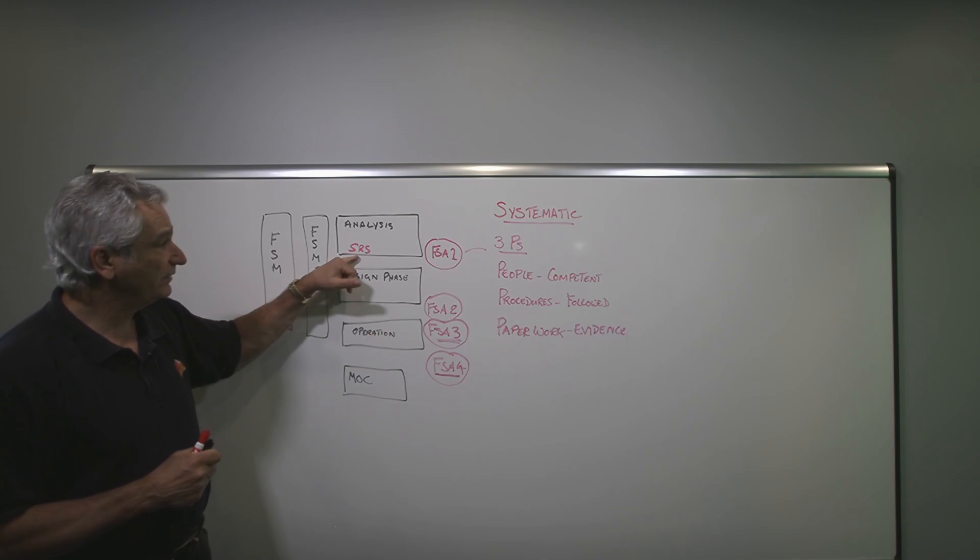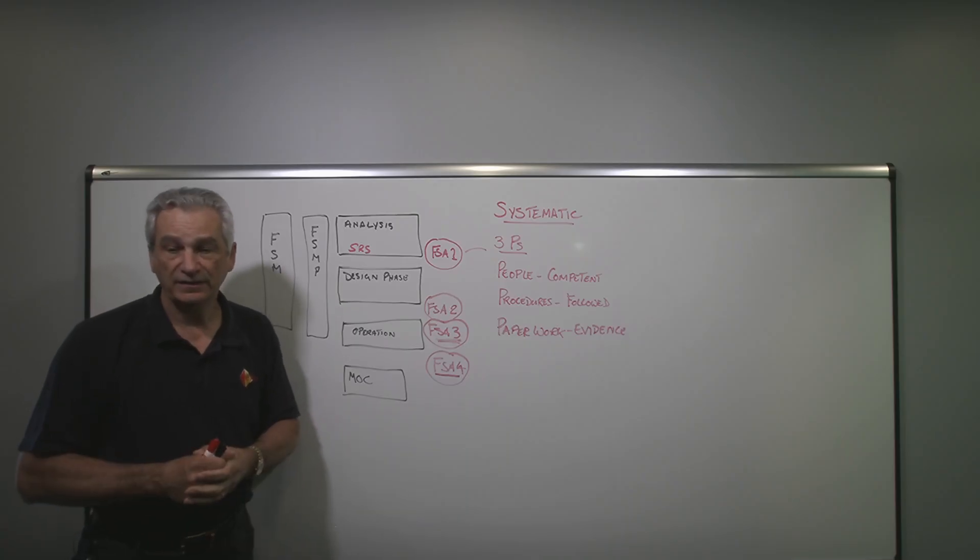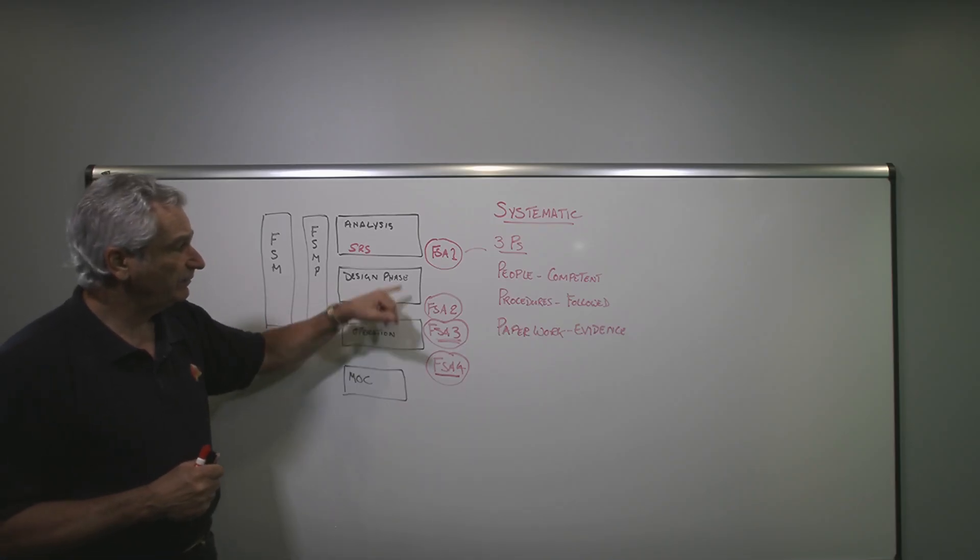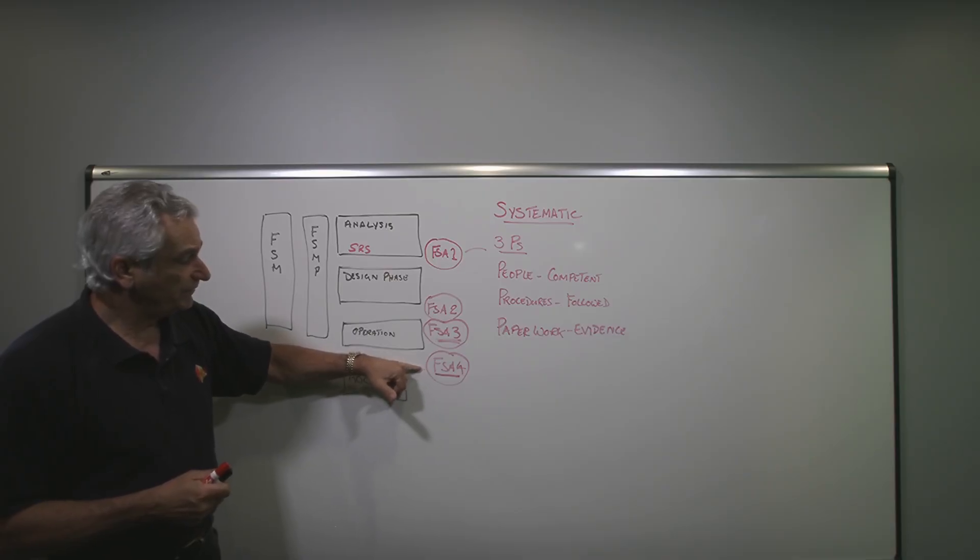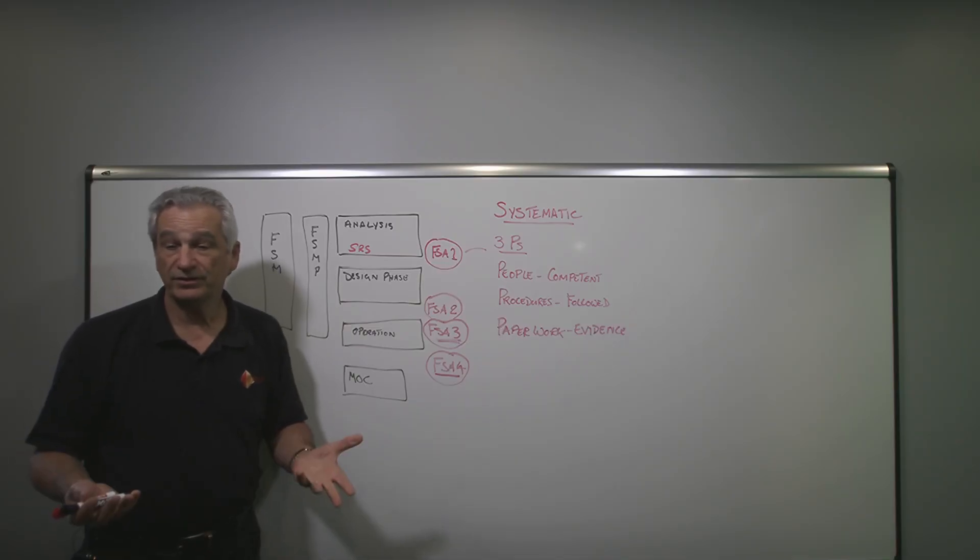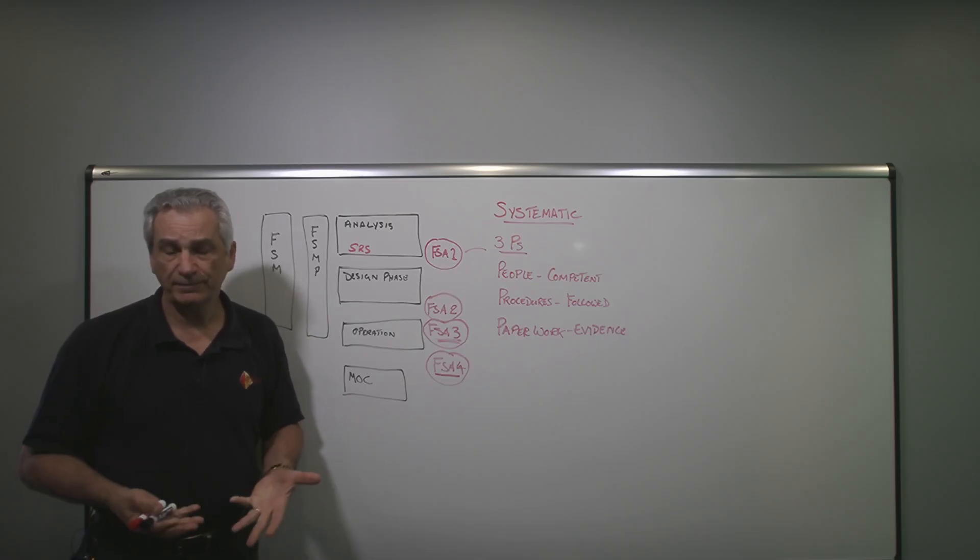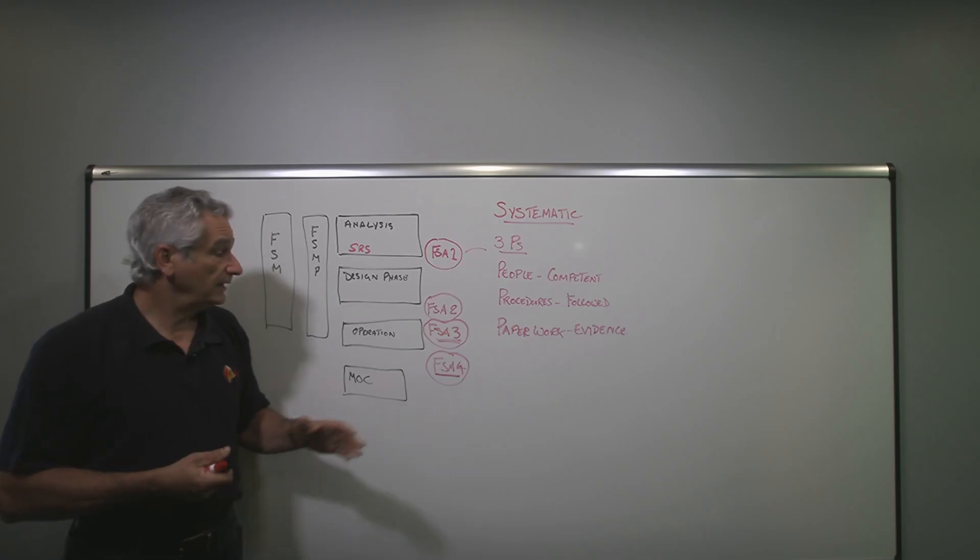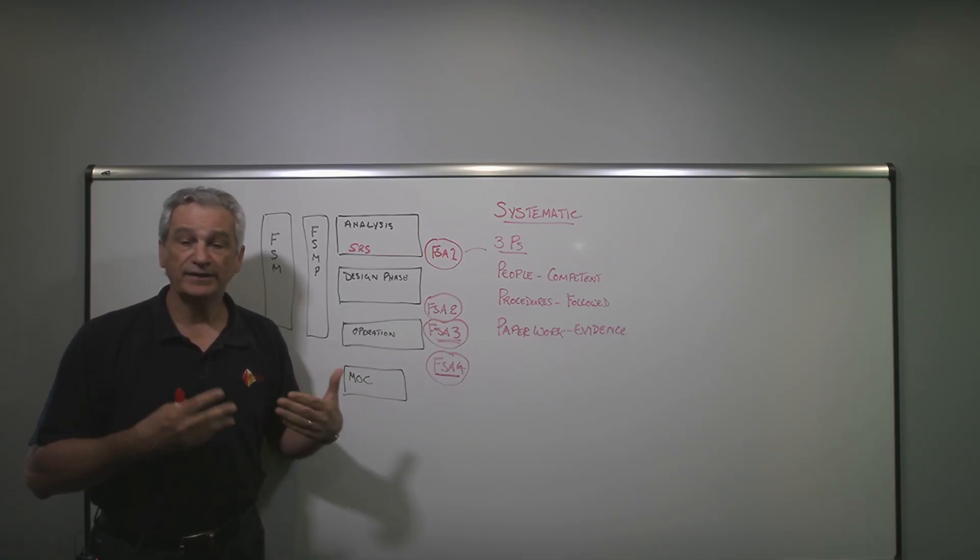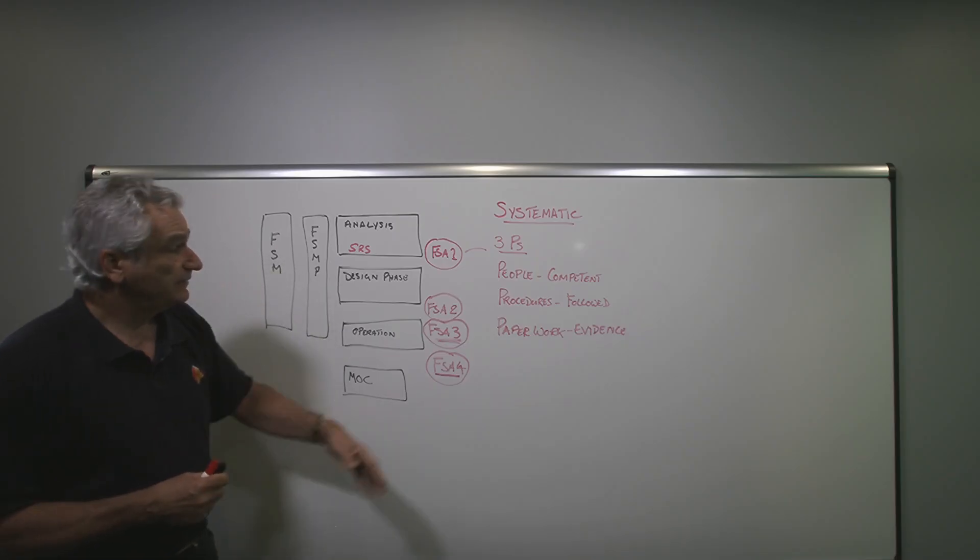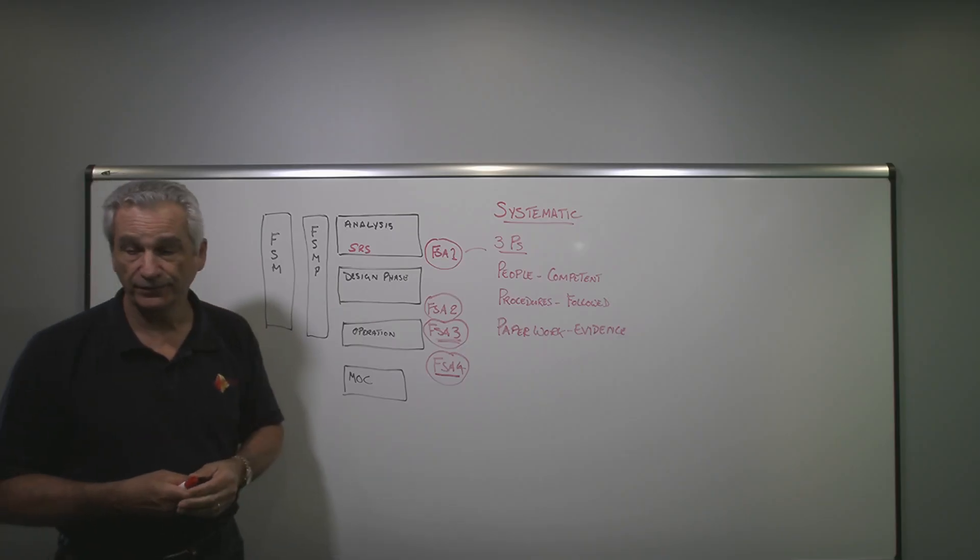We need to be able to look at our performance metrics. We can get a lot of the performance metrics from the SRS, such as the proof test interval, the mean time to restore, the mean time to fail safe, the spurious trips, the demand rates and so on. So we can measure and see, are we achieving that? And again, the other purpose of doing this is to also see, have we introduced any potential systematics as we've gone through here? If we're not documenting our proof testing, for example, if we're not keeping track with our maintenance, if we're not tracking our useful life, we're going to have problems. And again, if there are failures, if we do detect failures through the proof testing, have we done the proper analysis, which is the root cause analysis? We would need that evidence. And being able to track our performance is very important.